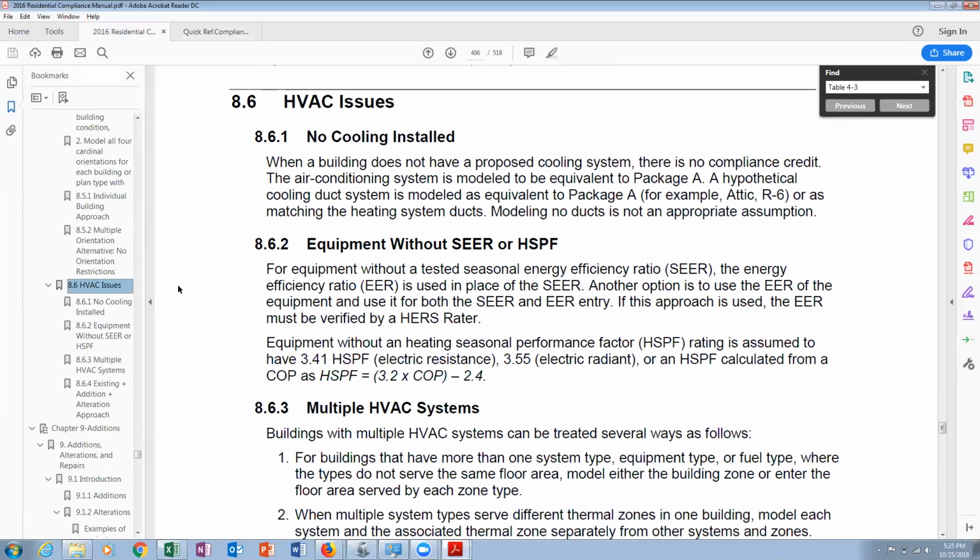So for example, Energy Pro and CBECC-RES are not very good at heat pumps. I think it's dominated by gas equipment in the building code. So when you're in the modeling software, you still can't really identify a really high efficiency heat pump or a really high efficiency heat pump water heater. I think the last cycle got a couple updates for NEEA rated water heaters, but still there's some workarounds that you have to do for sure as an energy modeler to get these high efficiency equipment to actually perform in the model the way that they're supposed to.